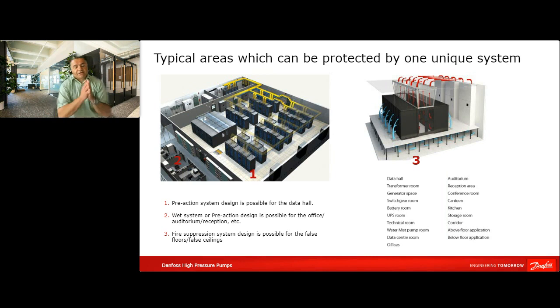Coming to a typical data center building, as you can see in both pictures, a data center building is a complex building. You have got different types of areas and rooms, and each area has got its own risk. What we want to show is that you can combine and connect, as previously said, all these areas into one unique high pressure water mist system. And the advantage is that you don't have to design, plan and purchase different extinguishing systems. If you look at the side view of a data center, in some projects you also have false floors or even false ceilings, and these areas are also part of the consideration when you design your system. So there are design differences and regulations that you have to follow, but everything within this building can be combined into one unique high pressure water mist system.